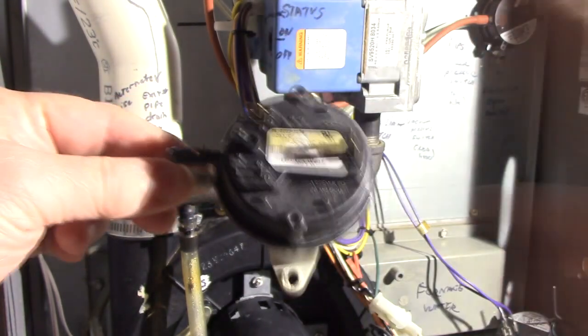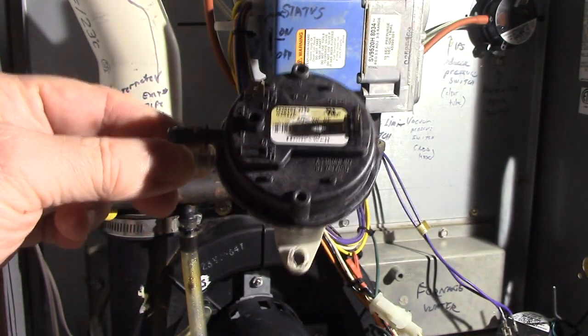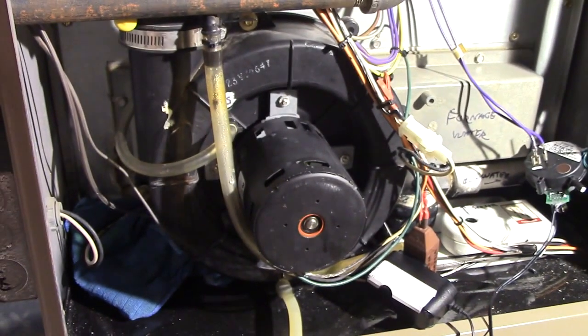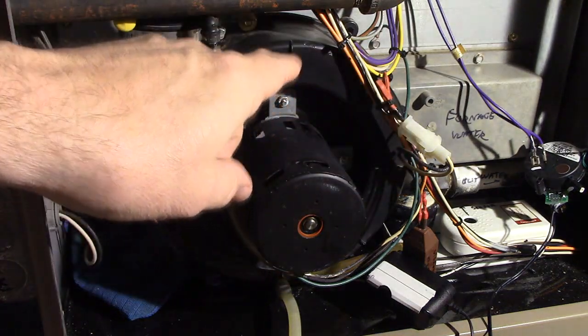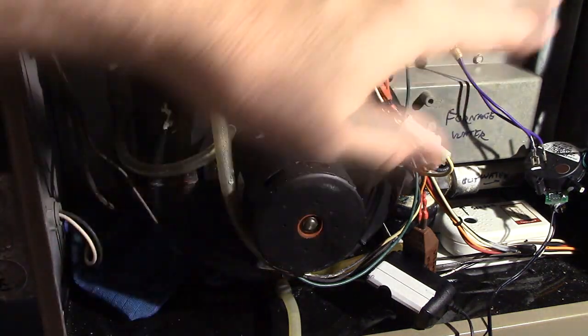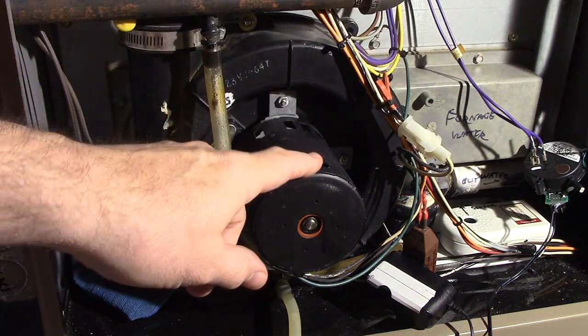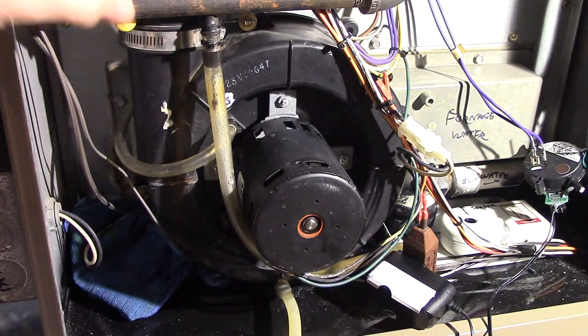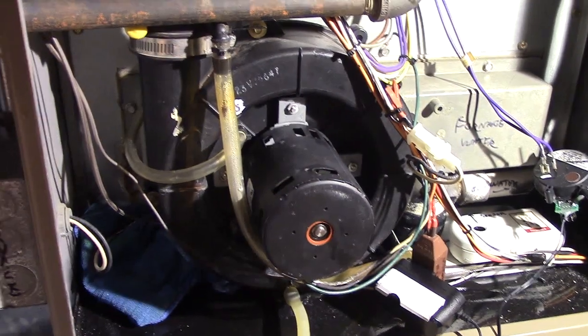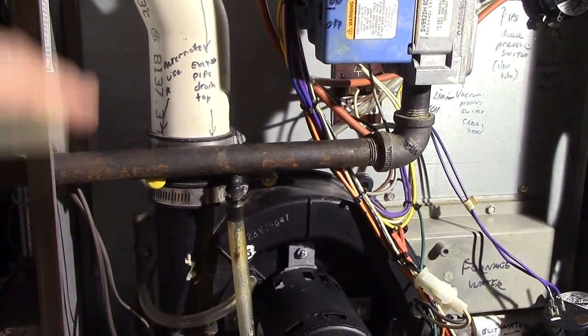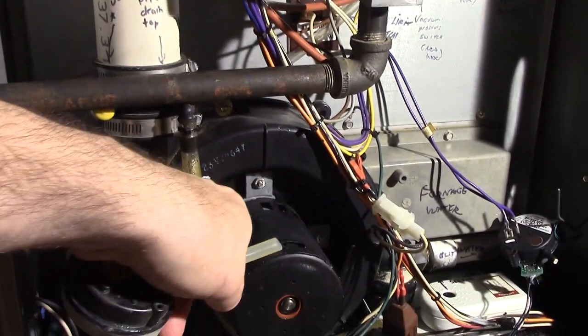looking at them, checking that they're not closed. It then turns on the inducer - you hear that loud whining sound on your furnace - and this makes sure the air is flowing through the heat exchanger, which is very important.